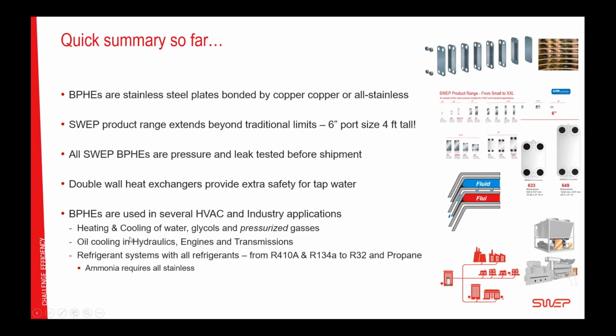And where you can find them, what kind of fluids. So heating and cooling of water, glycols, brines, and pressurized gases. Why do I say pressurized? Well, for an air dryer or a compressor where the air has been pressurized, it can pass through the heat exchanger without a problem. If you take ambient pressure air, for example, the brazed plate is not good enough. Then you need an air coil. But for pressurized gases, we can do it. Any type of oil, hydraulics, engines, and transmission oils, and then refrigerants. The two most common ones right now are R410A and R134A. The new ones come in. It could be R32 or propane, and brazed plates are good with all of them. Also, ammonia is possible, but since ammonia is aggressive to copper, all stainless heat exchangers are needed.